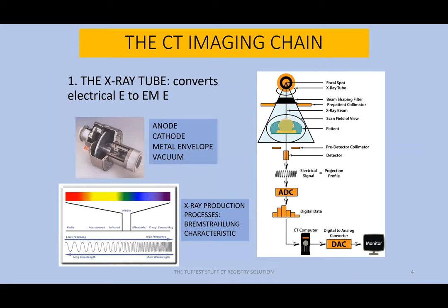We'll go through the components one at a time and we begin with the X-ray tube. As I go through the lecture and the slides, at certain points I'm going to say 'test answer,' which means the facts we're sharing are very important relative to a registry question — either as a question per se or as a potential answer. The X-ray tube — its primary purpose — test answer: its purpose is to convert electrical energy to electromagnetic energy.